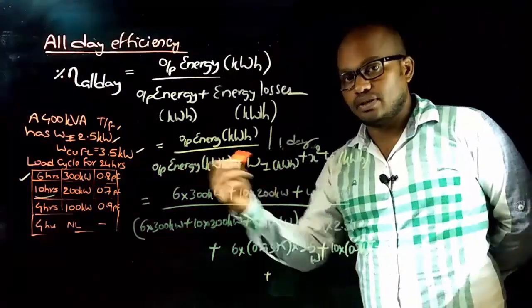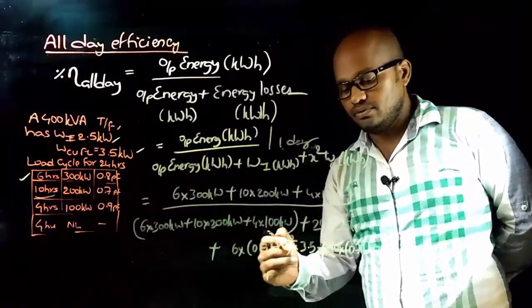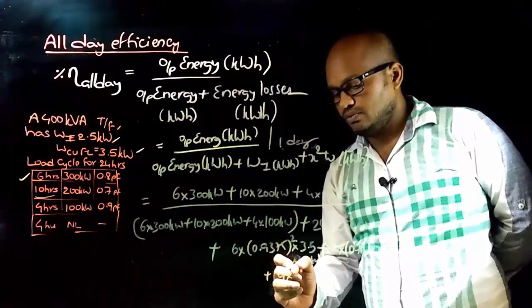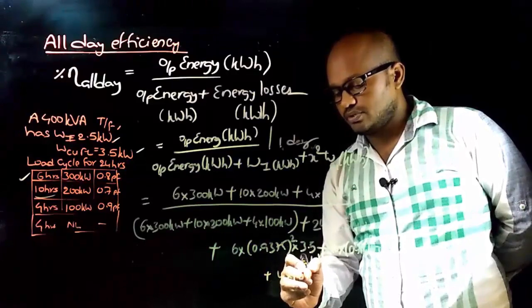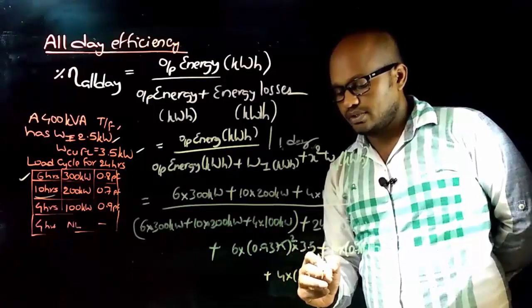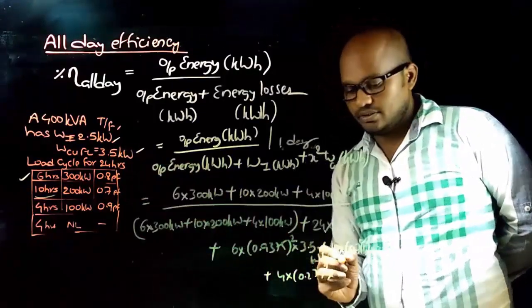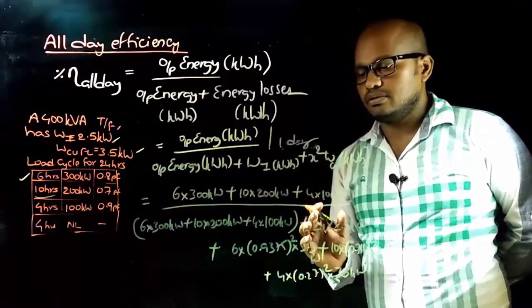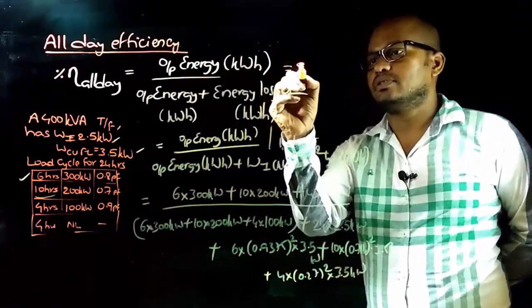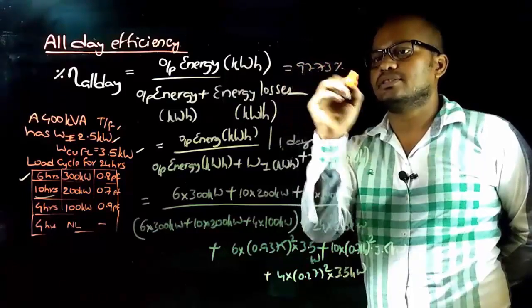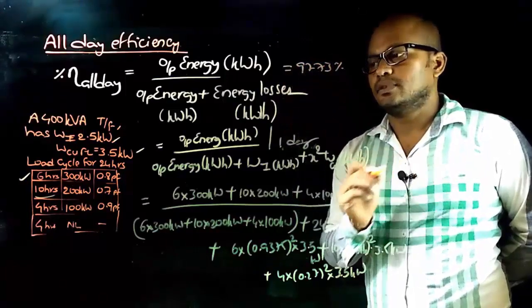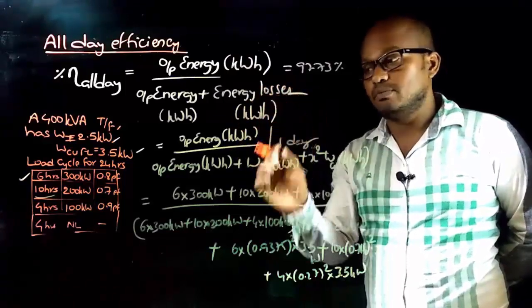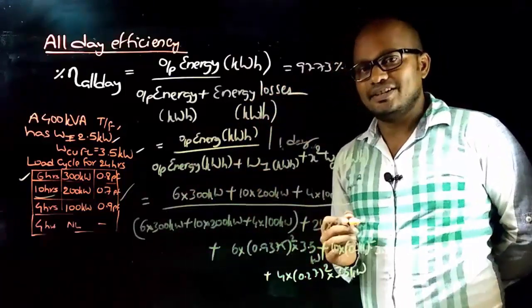For the next 4 hours, x is approximately 0.27, so copper loss = 4 × (0.27)² × 3.5 kilowatts. Solving the complete expression gives a percentage all-day efficiency of approximately 97.73%.